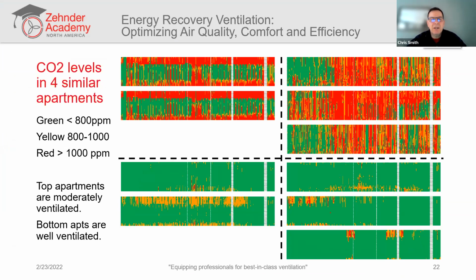1,000 parts per million of CO2 is sort of the recommended limit to be living with all the time. Above that, and you begin to experience degraded cognitive function. Could be pretty slight at first, just a little fuzziness or a little distractedness. But as you climb up, they've tested and they can see people have harder times making good decisions or processing more complex levels of information. So we want to stay below 1,000 parts per million. The yellow in these charts is a range between 800 and 1,000 parts per million. And then the red is above 1,000 parts per million.